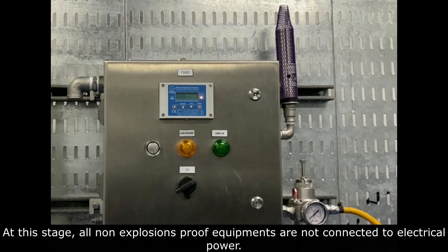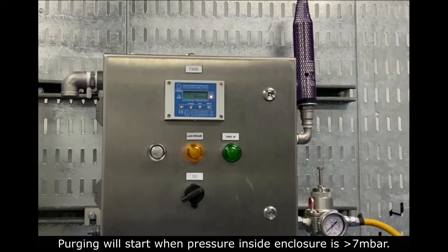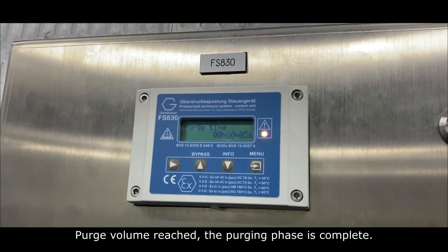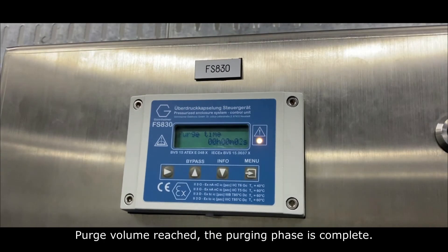At this stage, all non-explosion-proof equipment are not connected to electrical power. Purging Phase. Purging will start when pressure inside the enclosure is more than 7 millibar. The purging process is controlled by the control unit. Purge time will start countdown. Purge volume reached — the Purging Phase is complete.